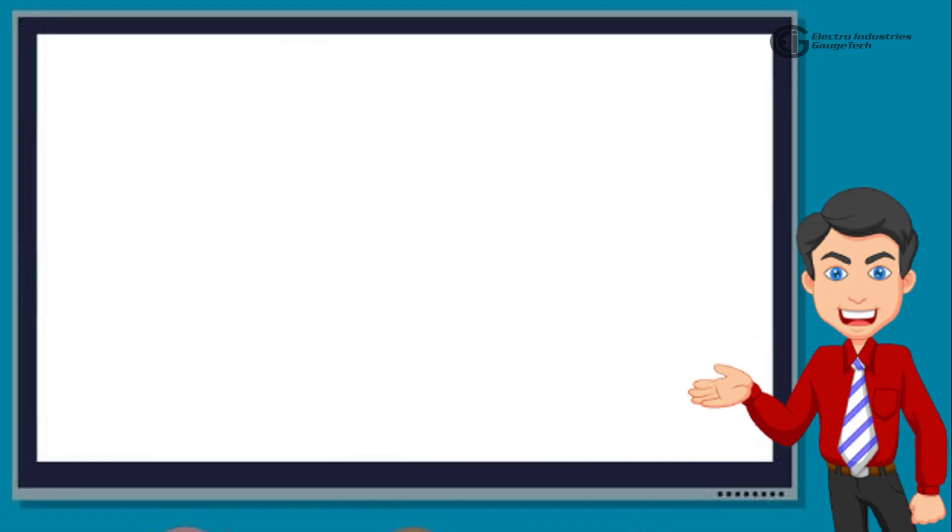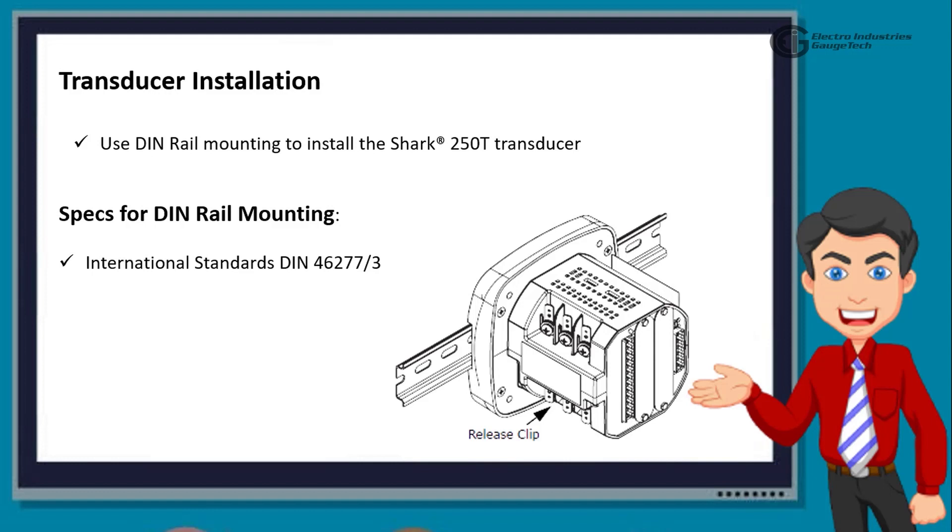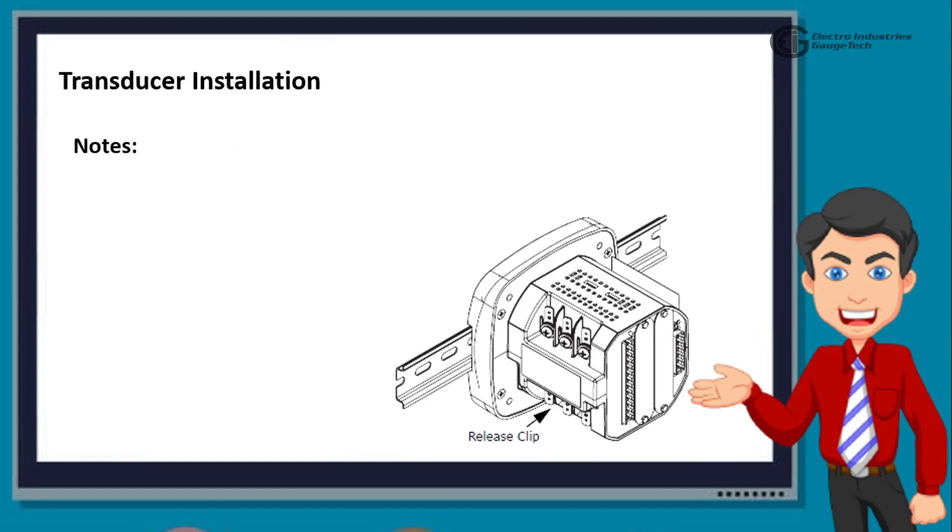Moving on to the next one, we have the transducer installation. Here, use the DIN rail mounting to install the Shark 250T transducer. The specifications for the DIN rail mounting are international standards DIN 46277/3. The DIN rail slotted dimensions are 0.297244 inches by 1.377953 inches by 3 inches or 0.755 centimeters by 3.5 centimeters by 7.62 centimeters. Now, slide top groove of meter onto the DIN rail. Then, press gently until the meter clicks into place. Please note that, to remove the meter from the DIN rail, pull down on the release clip to detach the unit from the rail as shown in the diagram here.